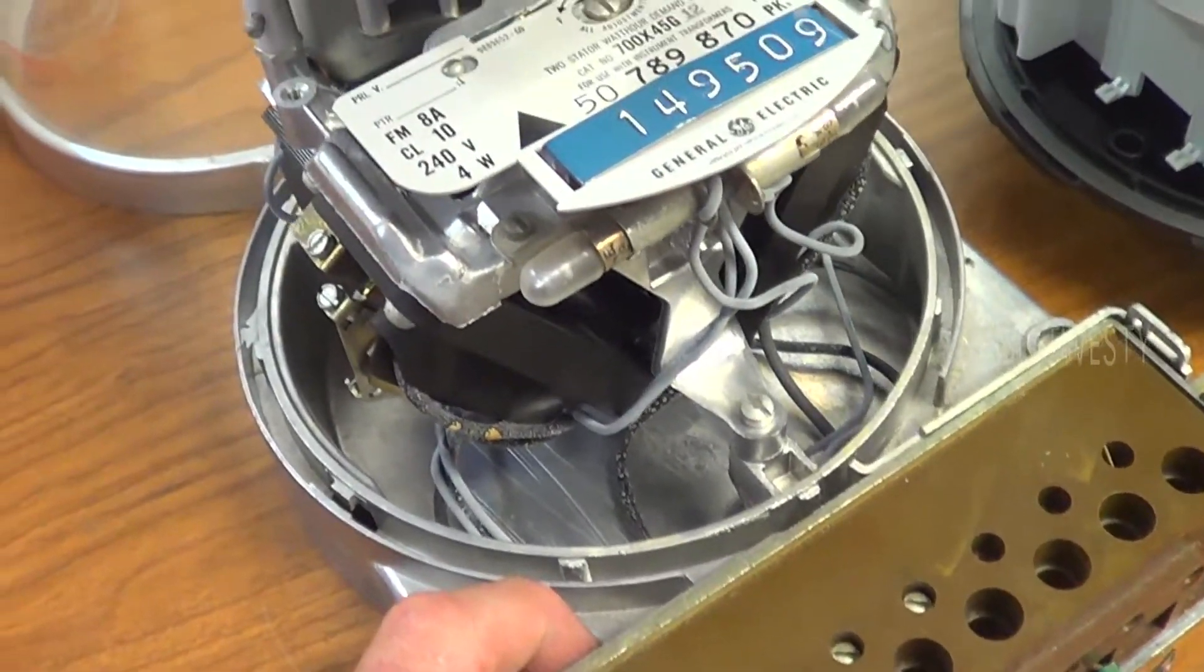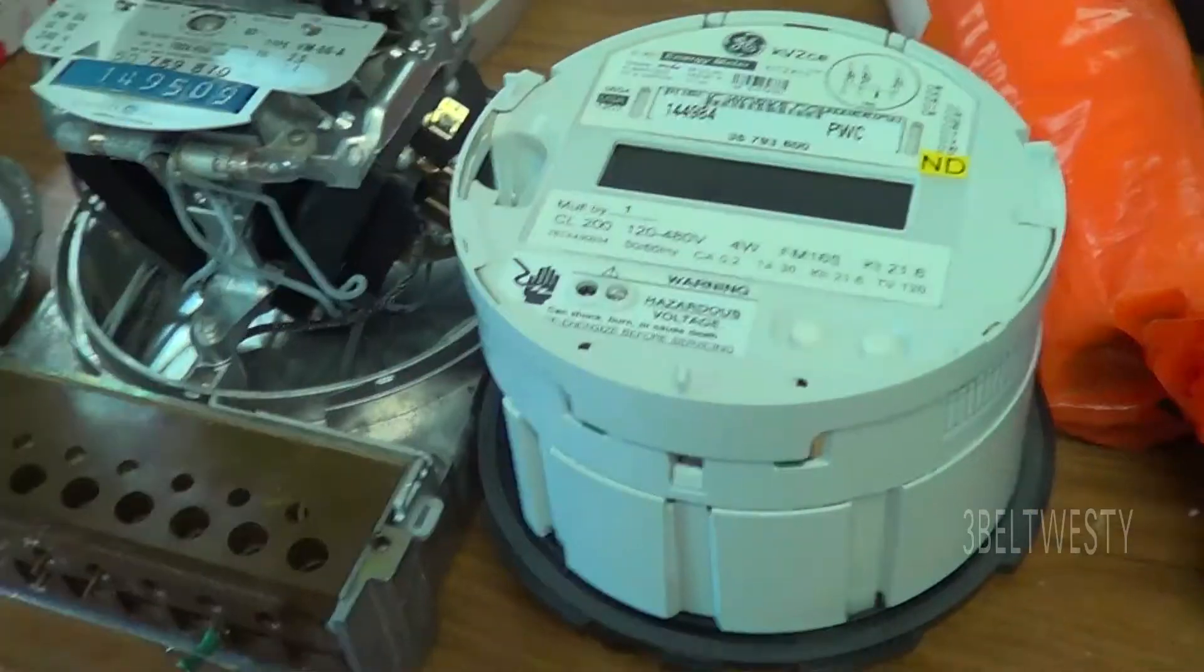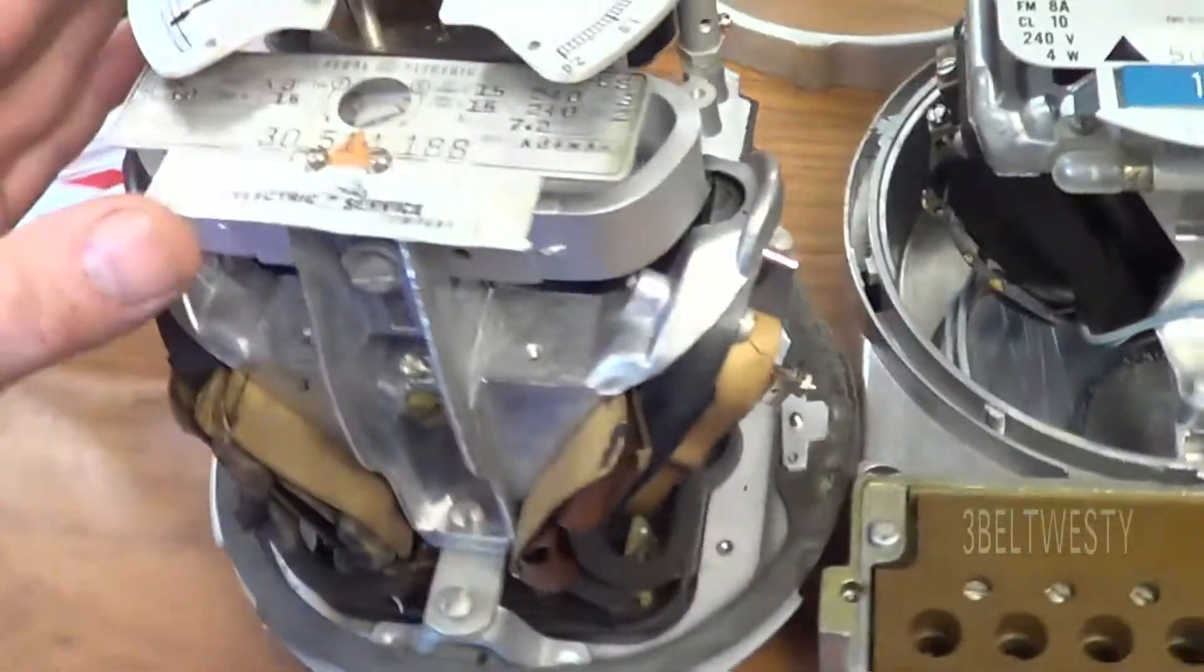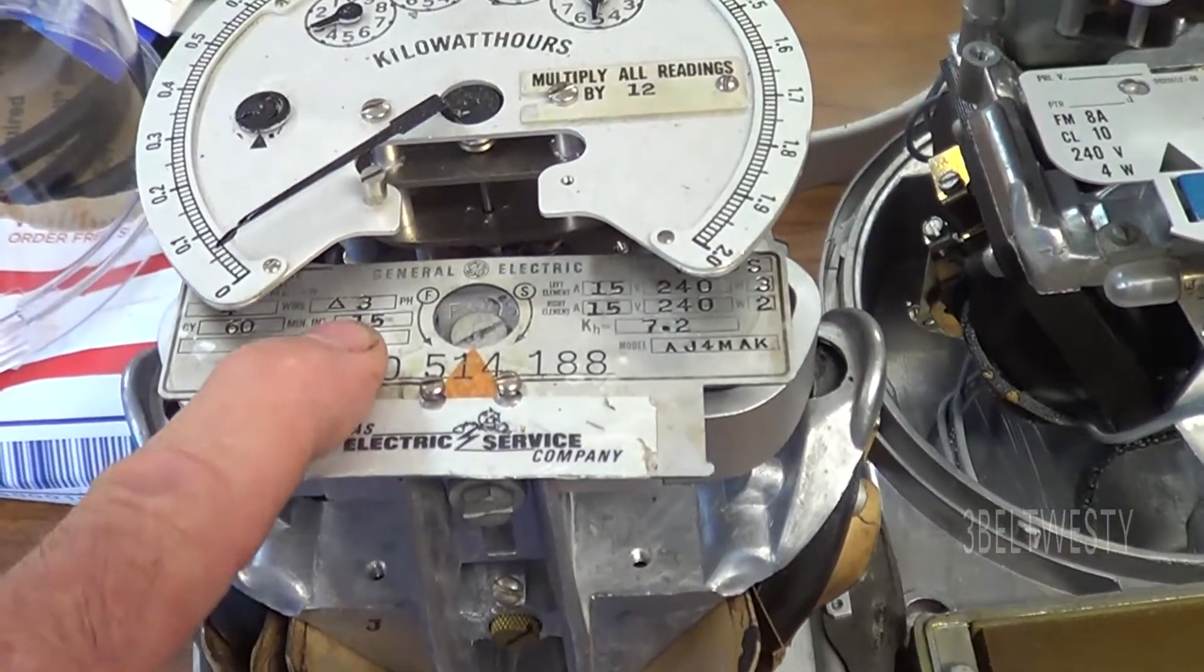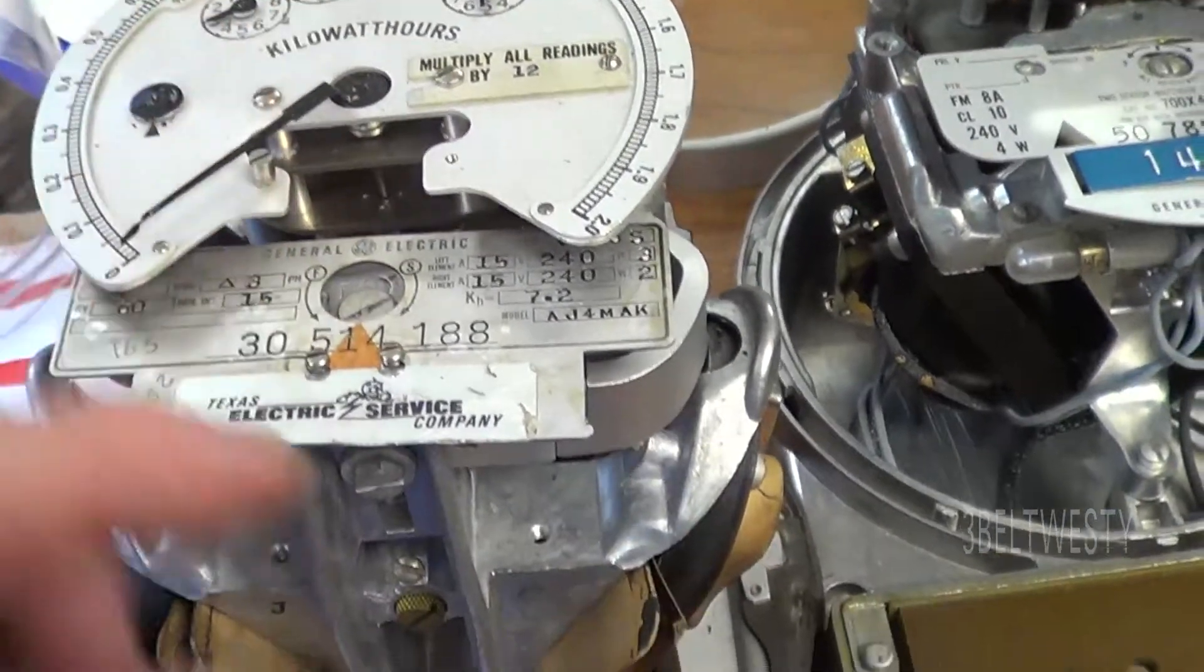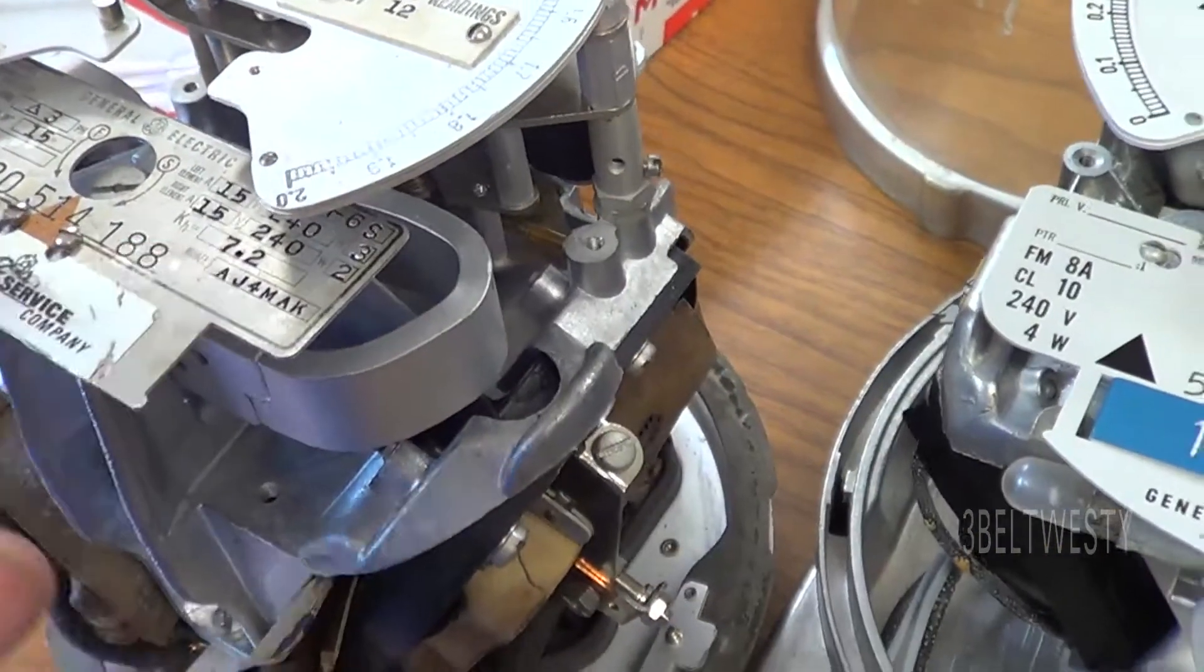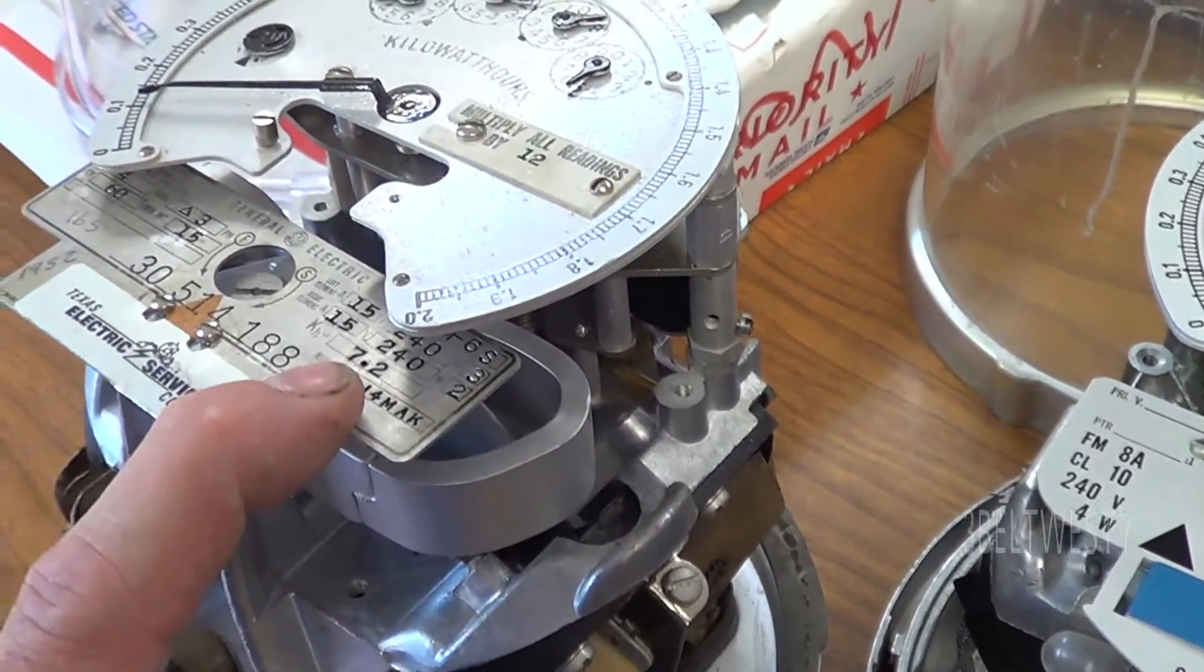That is a demand meter. You can see how small this meter is here. Older meters mechanical are bigger. Here's one from a Texas service company from 1952. This is three phase, it has a demand, it will go up and this particular model here actually is not transformer rated. It's a 15 amp device on generally in this type of service from the 50s.